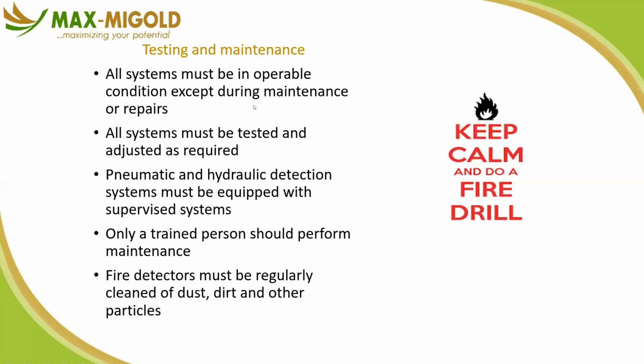You are about to position the fire extinguishers. What if fire happened in this room? Will I be able to use this extinguisher? That tells you, oh, let the extinguisher be close to the exit door, because if fire happens, everybody will go towards the exit. Some even put the extinguishers in the corridor, outside the space or room where they want to use it, provided it won't reduce the walkway, because that would be a health and safety risk when people hit their side or hand against the fire extinguishers. So you need to do that what-if analysis to know what other things you need to do.